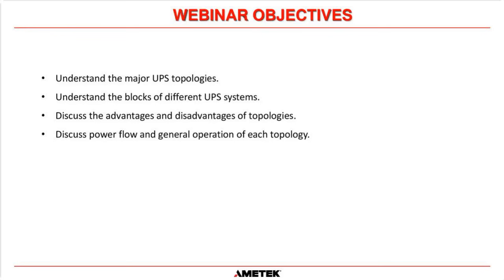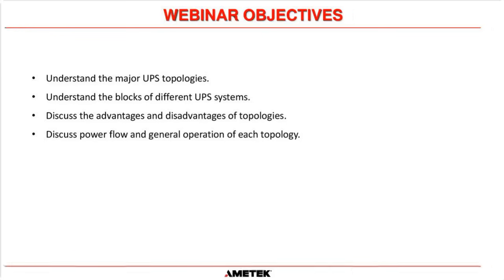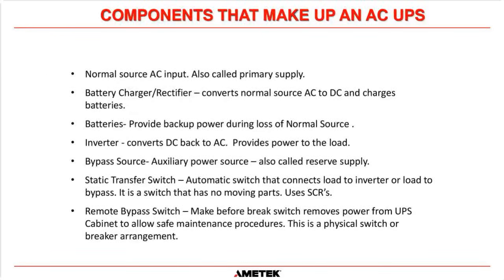Okay. So the first thing we're going to go over is components that make up an AC UPS. And when I say an AC UPS, I mean a UPS that has an AC output rather than a DC output. So first of all, you have your normal source AC input, which is also called the primary supply, or if you're in Europe, it's called the main supply. But that is usually, for most industrial systems, a three-phase 480 volt input to the UPS.